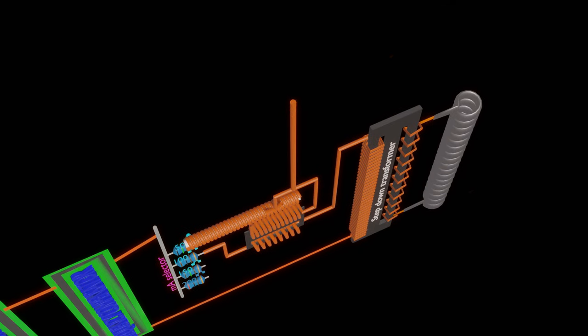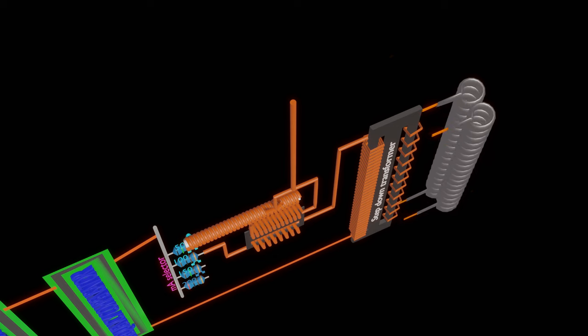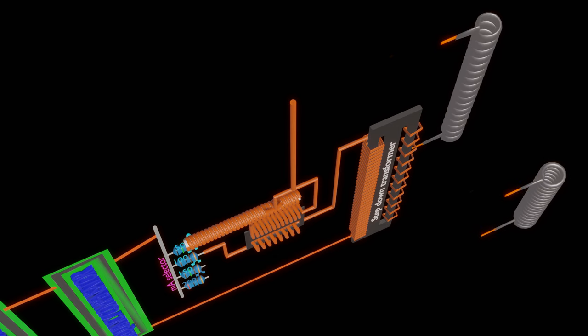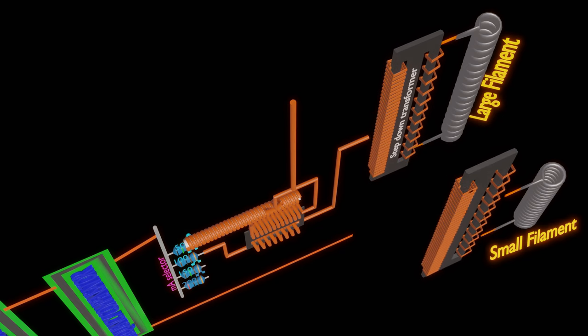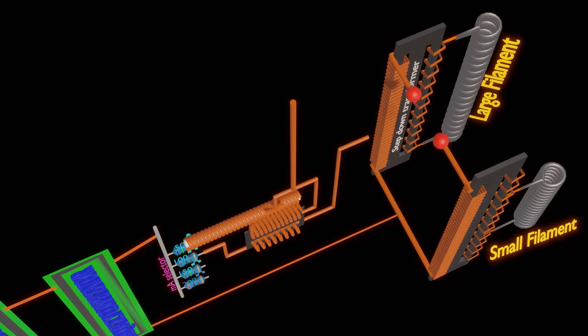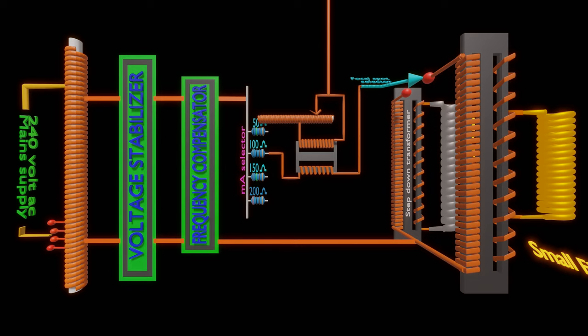For X-ray tubes having two filaments, one being small and the other being large, each filament will have its own filament transformer. A focal spot selector is to be incorporated in the circuit for switching between the filaments. This is all about different components of a filament circuit.